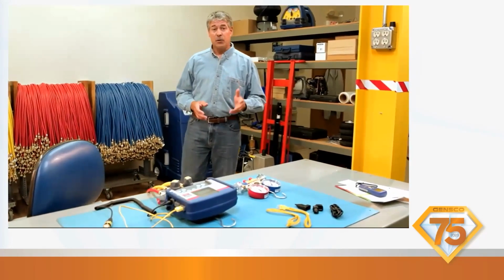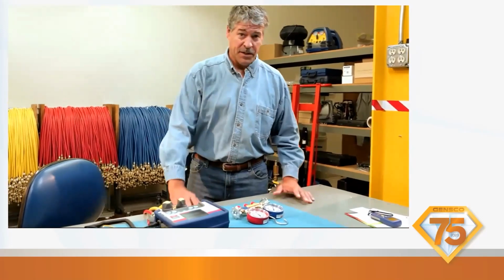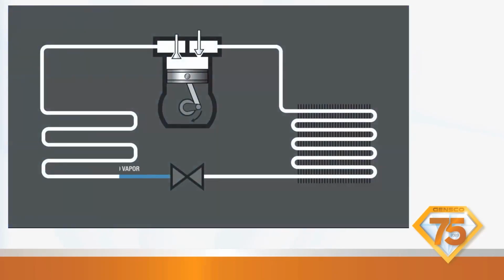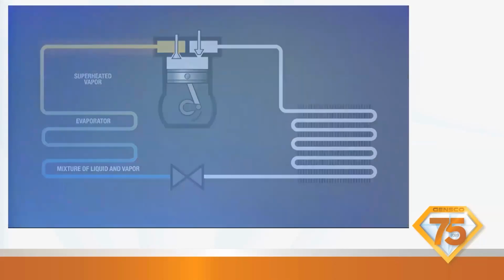A working knowledge of superheat and subcooling is as critical to technicians as our working tools and equipment. Hi, it's Paul again. Measuring superheat and subcooling is essential for optimal performance of a refrigeration system. First, let's look at superheat. As refrigerant enters the evaporator, it's in a liquid state. As heat is added to the liquid, it will turn to a vapor at its boiling point, or saturation temperature. After the refrigerant has boiled to vapor, any temperature of the vapor above the saturation temperature is the superheat. Superheat is then any temperature of a gas above the boiling point for that liquid.